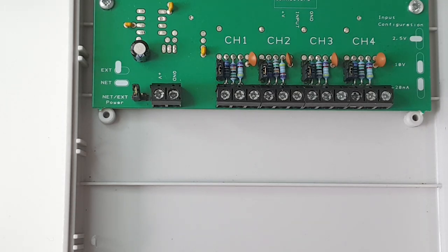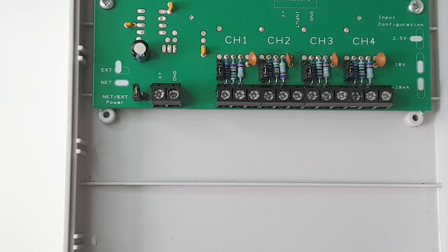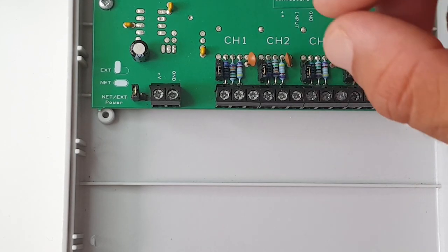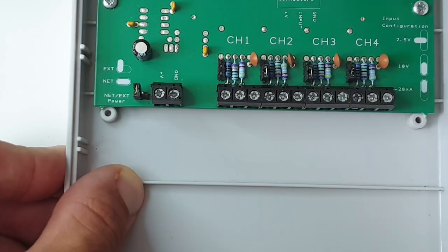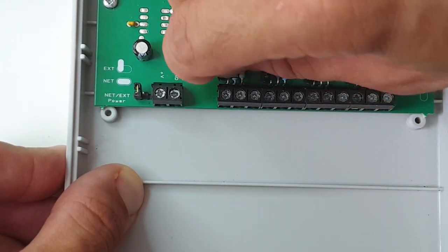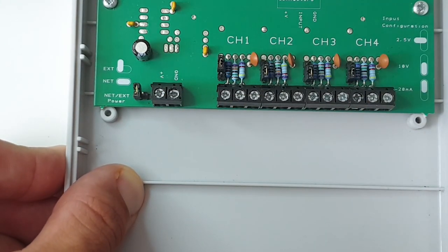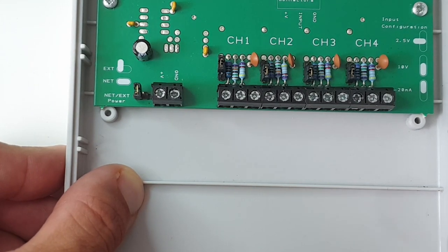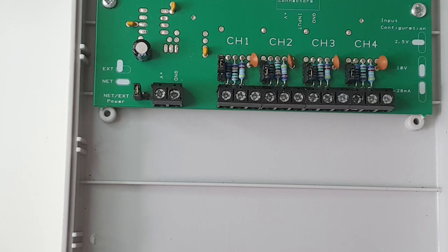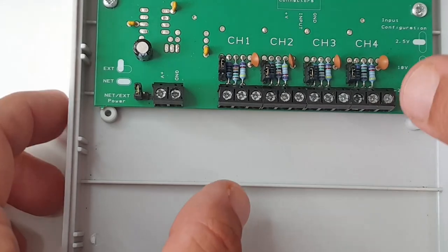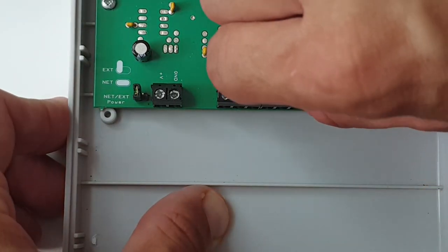So if we wanted, for example, to have 4-20 milliamps on the first channel, we take the jumper out and put it across the top two pins. And that makes it 4-20 milliamp. And if we wanted to do channel two as 2.5 volts, you can either take the jumper off and just connect it to just one of the pins, it doesn't matter which one, just so you hold it in place.